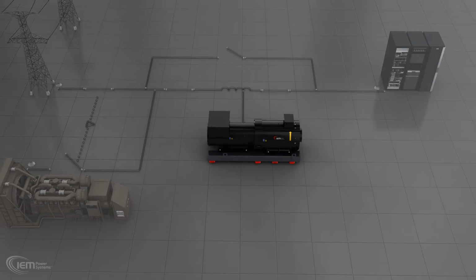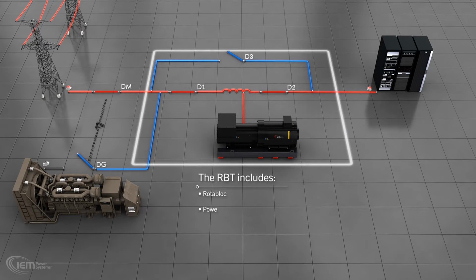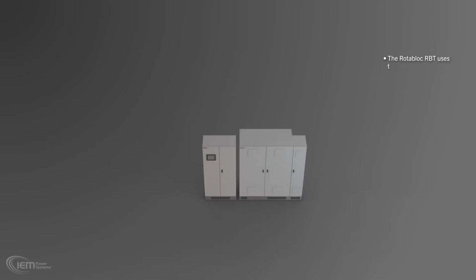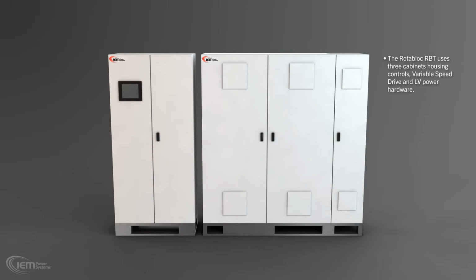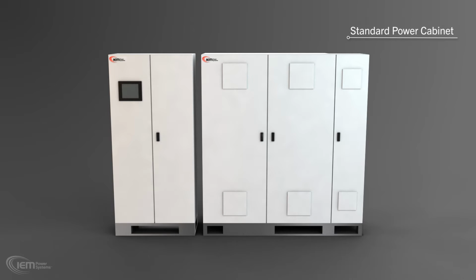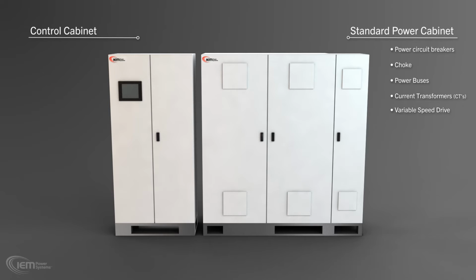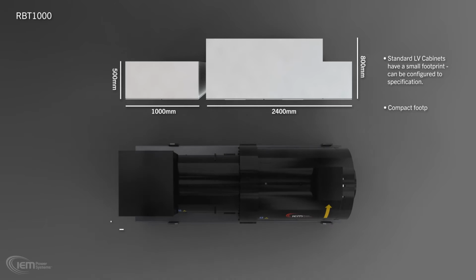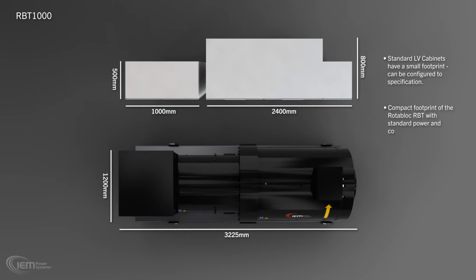Power and control cabinets are supplied with the Rotabloc and can also be integrated into the full switchgear lineup. The IEM Power Systems RBT is defined in this diagram. The Rotabloc RBT typically employs 3 cabinets to house the controls, variable speed drive, and LV power hardware. IEM Power Systems are experts in providing power solutions up to 38 kV to meet the requirements of your facility. The standard Rotabloc power cabinet contains power circuit breakers, choke, power buses, current transformers, and the VSD. The Rotabloc control cabinet contains a touchscreen HMI, power metering, mini circuit breakers, backup auxiliary power supply, and the main PLC. The standard LV cabinets have a small footprint and can be readily configured to your exact specification. Note the compact footprint of the Rotabloc RBT with its standard power and control cabinets.